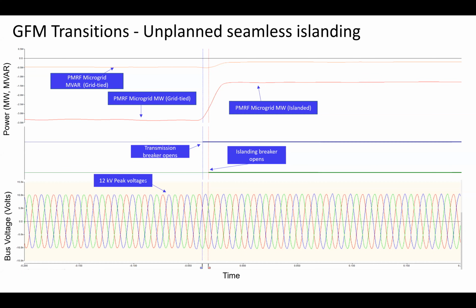In reality though, when a fault happens and protection opens unexpectedly, it does depend on the type of fault and what the AES plant is doing at that time to help the grid. What are the dispatches, how much sun is available. There are a bunch of different conditions, but we have seen that it's possible to do an unexpected islanding. There are a few scenarios where it might not work out this way, where we remain online. We might actually drop off, go offline, everything goes black, and then we would have to Blackstart.